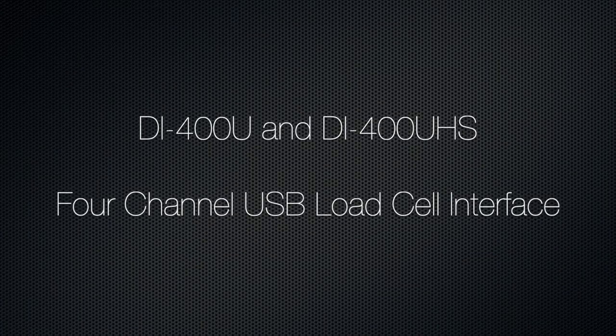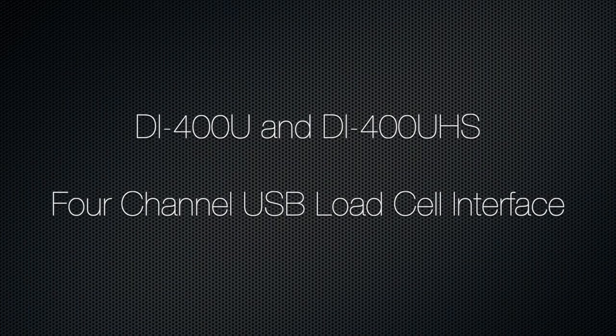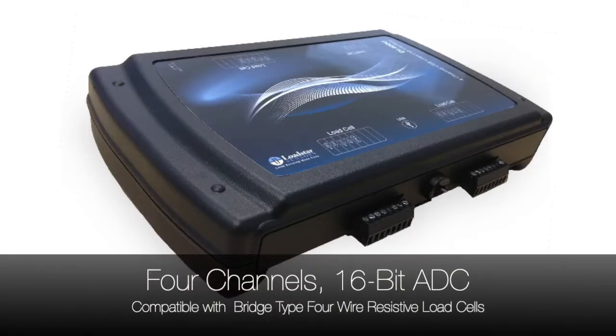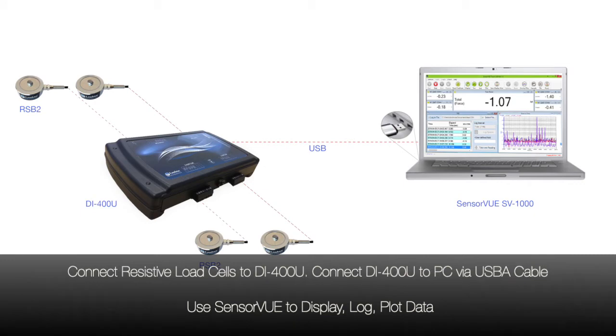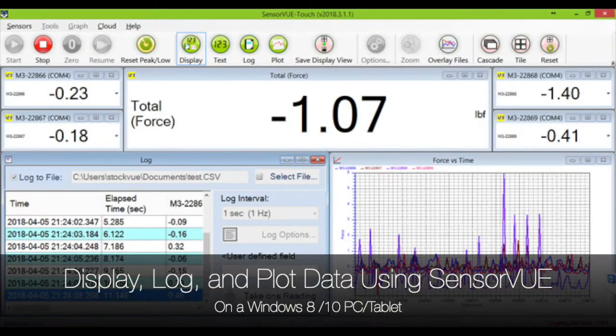DI-400U is our 4-channel USB load cell interface. This interface has a 16-bit ADC and can give you approximately plus or minus 0.1 percent of full scale or better accuracy. You can connect 4 load cells and use SensorVUE software on a PC or tablet running Windows 8 or 10 to display, log and plot data from all 4 sensors simultaneously.